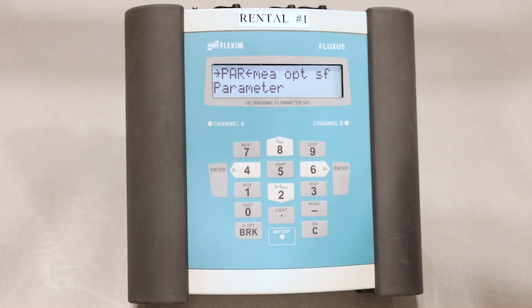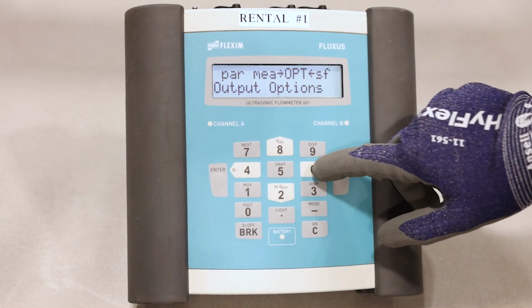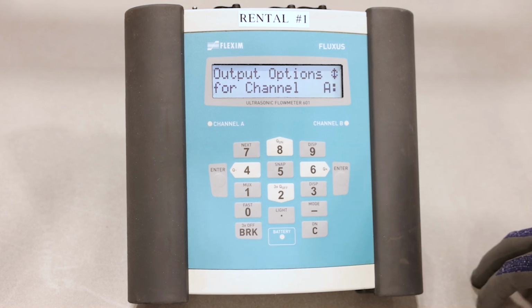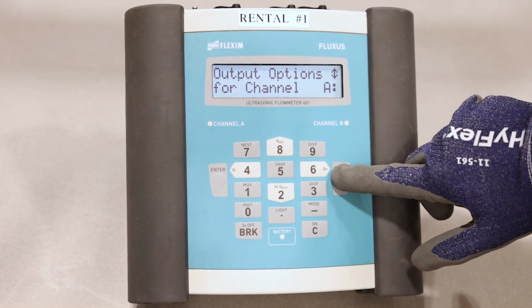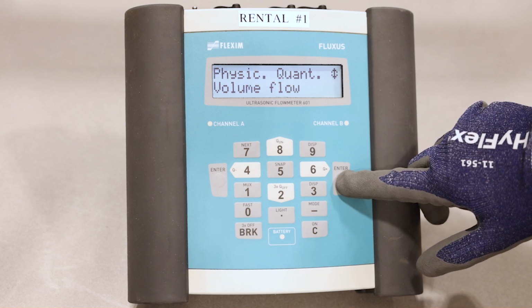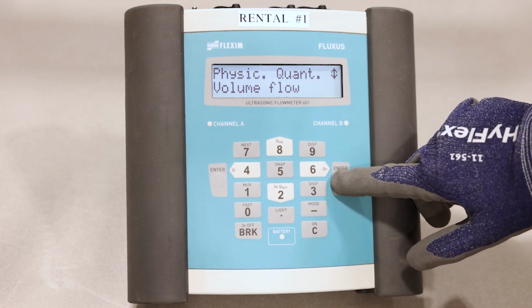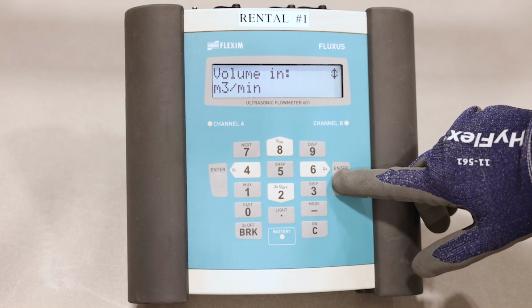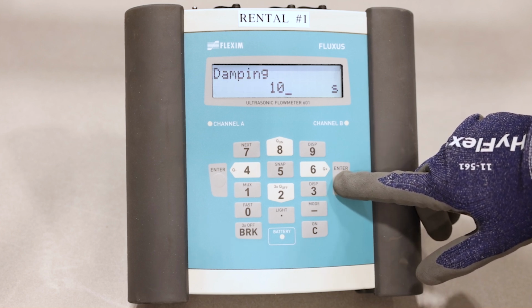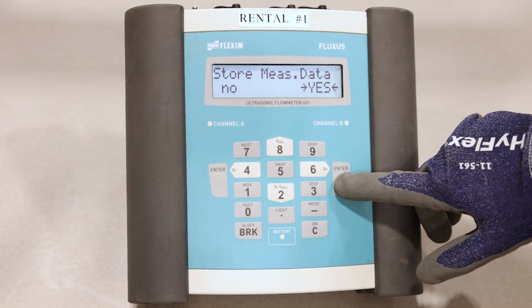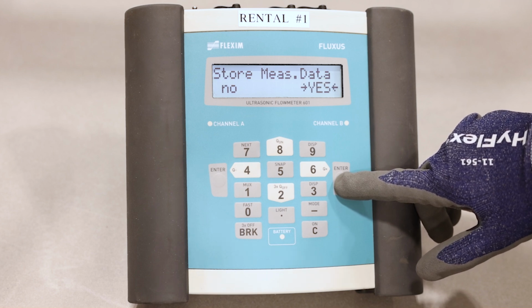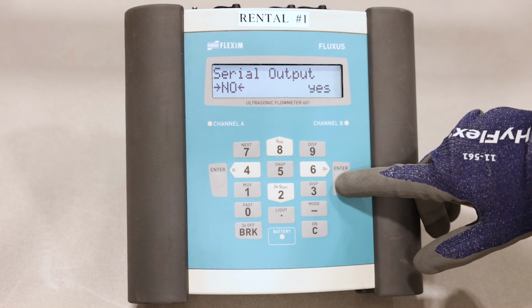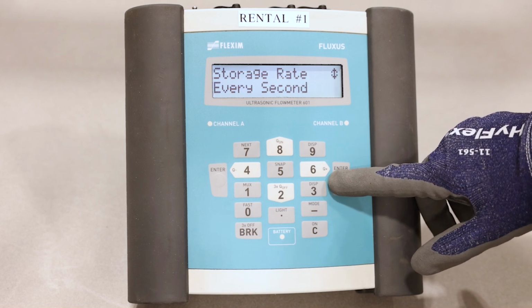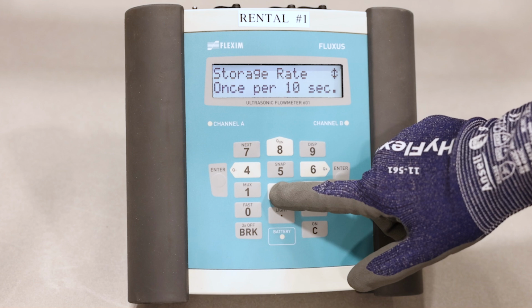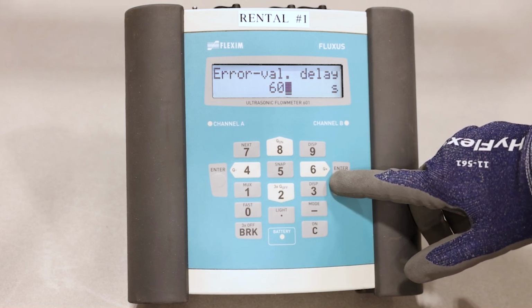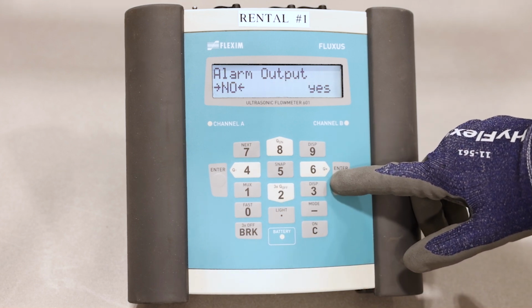We will start by setting the flow units in the output options menu. Scroll over and press enter. Here, we will select our desired channel, in this case, channel A. For this setup, we will pick volume flow, meter cube per minute, damping of 10 seconds, store measure data. For data logging, let's pick yes, no for serial output, set the storage rate for every 10 seconds, error delay to default of 60 seconds, and alarm output to no.